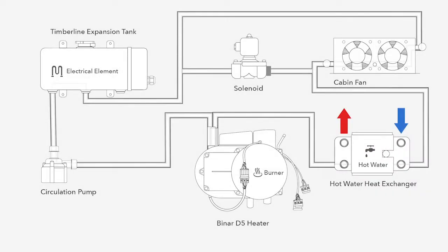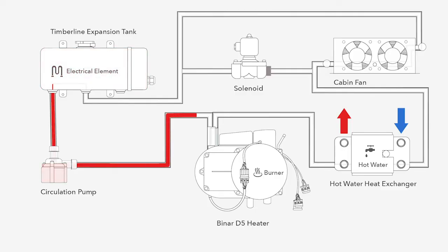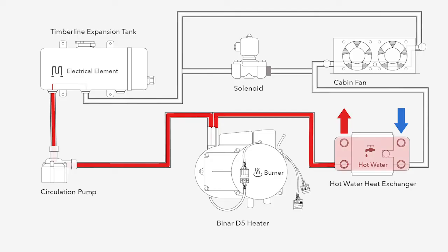I'm going to pull up this diagram to give a better understanding and visualization of the system itself. The glycol starts in the expansion tank — this is where the electric element sits. The glycol then goes to the circulation pump where it is pumped into the diesel heater, our primary heat source at 17,000 BTUs. From the heater, the glycol goes to the heat exchanger, where your cold domestic water comes in and your hot water comes out. This is where all your hot water for your showers and sinks is created.